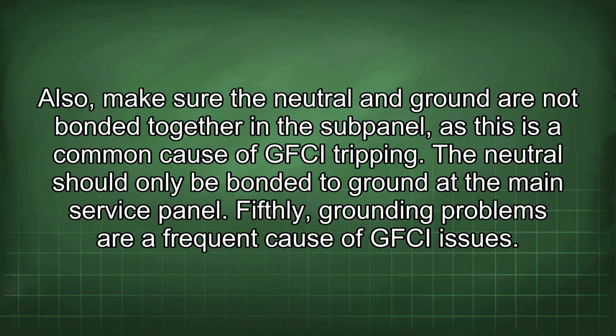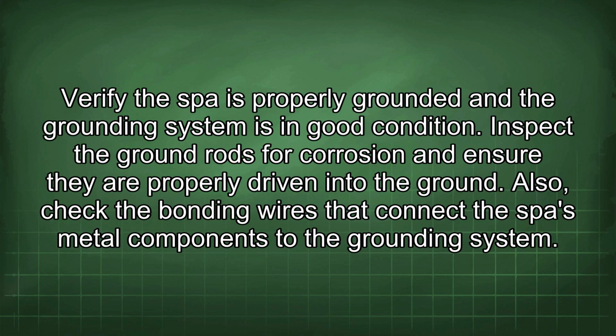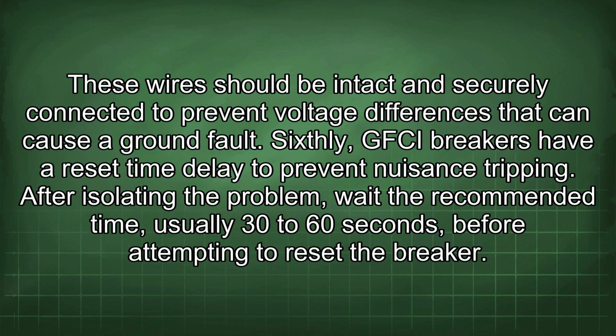Fifthly, grounding problems are a frequent cause of GFCI issues. Verify the spa is properly grounded and the grounding system is in good condition. Inspect the ground rods for corrosion and ensure they are properly driven into the ground. Also, check the bonding wires that connect the spa's metal components to the grounding system. These wires should be intact and securely connected to prevent voltage differences that can cause a ground fault.